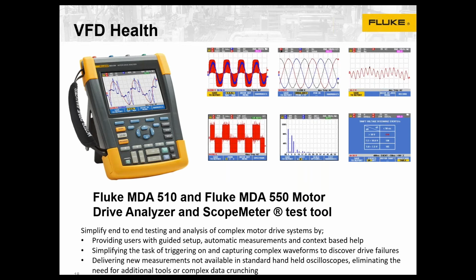A tool called a motor drive analyzer helps automate that process. Most customers are not VFD experts. And what this tool does is provide a simple, easy, menu-driven interface as to what measurements to make on drives, where to make them. It will show you images on how to hook up probes. It will automatically set itself up to make the proper measurements and then allow you to save those measurements for documentation purposes. So it is essentially a guided setup and guided usage of the tool to help speed that up and also to be more proactive so that if you do have an issue, you can do some quick comparative testing to a baseline.